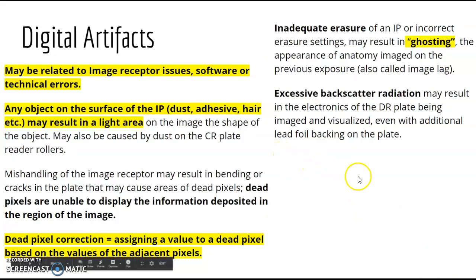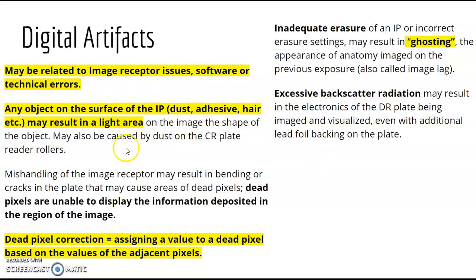Your digital artifacts may be related to image receptor issues, software technical errors, or any object on the surface of the imaging plate — it could be dust, adhesive, hair, etc. It's going to result in a lighter area on your image in the shape of the object, whether it's dust on the CR plate, dust on the rollers, or tape on the rollers.